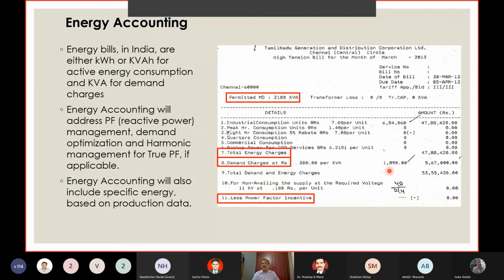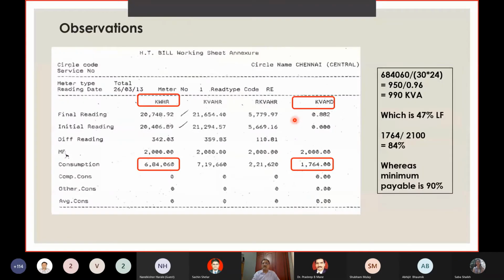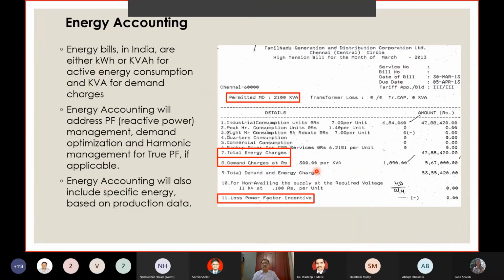So this is one area where 1890 is 90%. So 2100 is sanctioned. So what happens here? We are actually paying 336 kVA additionally. At that time, this was 300 rupees per kVA. Today is 350 rupees. See, it's 2013. So it is 350 rupees per kVA. So approximately 1 lakh rupees every month they are paying for an additional demand.